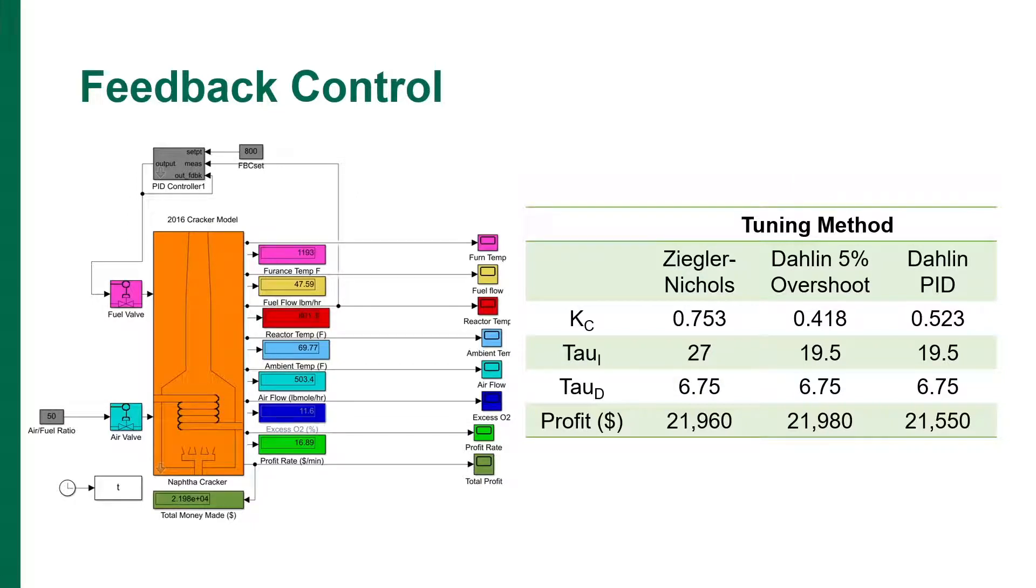The first type of control that we implemented to control the reactor temperature was feedback control of the proportional integral derivative or PID type. Among other variables, the reactor temperature measurement is dependent on the amount of fuel fed to the furnace. So this measurement is compared to a set point of 800 degrees Fahrenheit, which then results in the controller manipulating the fuel valve, which is normally 50% open.